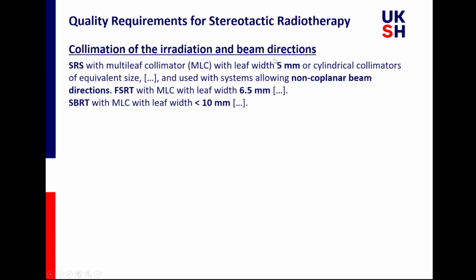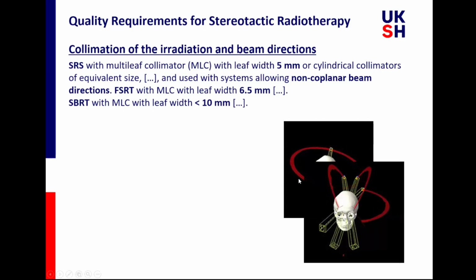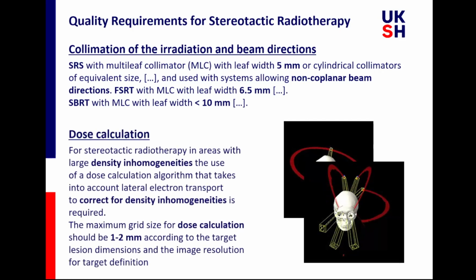And we want this, of course, also to be very precise. So generally 5 millimeters. Here, collimator, multi-leaf collimator or small cylindrical collimators needs to be used. We want the leaf width to be smaller than 10 millimeters for extracranial targets and smaller than 6.5 millimeters for intracranial targets to actually capture the very small, tiny tumors that we often treat. For example, brain metastases are 3-4 millimeter wide, and we, of course, need to make sure that the system can actually accommodate those tumors. And here, for example, also from many beam directions, not just one beam direction, but from different planes, non-coplanar beam directions is required to have a better dose distribution, for example, and also the dose calculation needs to be super accurate. We want a grid size of 1 to 2 millimeter according to the target lesion. Of course, in the brain, 1 millimeter, extracranial 2 millimeter might be okay.